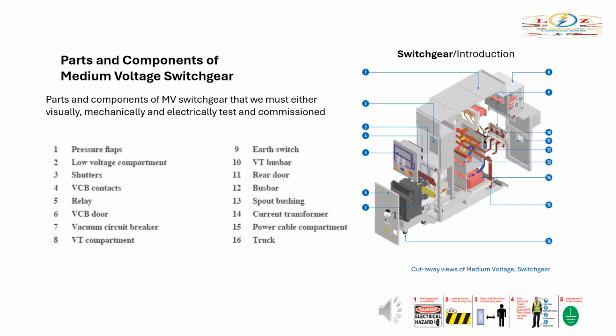Parts and components of MV switchgear that we must visually, mechanically, and electrically test and commission are as follows. 1. Pressure flaps. 2. Low voltage compartment. 3. Shutter. 4. VCB or SF6 contacts. 5. Relays. 6. VCB or SF6 doors. 7. Vacuum circuit breaker or sulfur hexafluoride. 8. VT compartment. 9. Earth switch. 10. VT bus bar. 11. Rear door. 12. Bus bar. 13. Spout bushing. 14. Current transformer. 15. Power cable compartment. And 16. Truck. Also, metering and its control wirings, to verify first the point-to-point check.